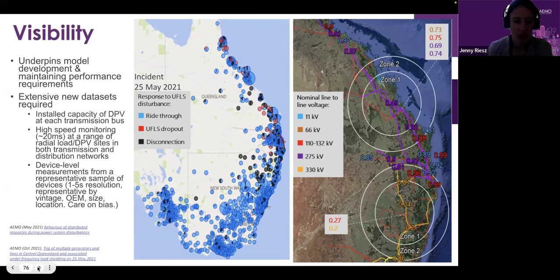To do this kind of analysis requires enormous new data sets. You need device-level monitoring from a sample of inverters, which is how we produced that figure on the left. We need much improved monitoring of voltages, high-speed monitoring across the grid, and active and reactive power, which was the data set used to produce the figure on the right. You also need to know the installed capacity of PV at each transmission bus, which is highly non-trivial. These are just three data sets where we have some patchy coverage, but we're working hard to improve them because they're so crucial in underpinning everything we're doing.